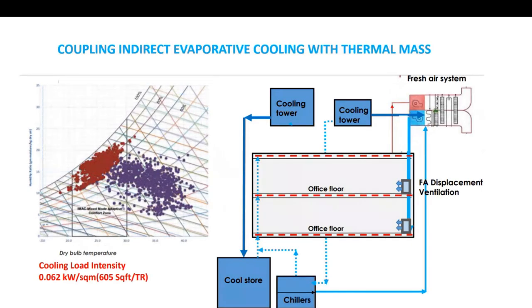Making use of the very dry climate of Hyderabad, we install a highly efficient cooling tower, which has about a 1 to 2 degree approach to wet bulb. We store that cool water in a big store in the basement, and this water is then circulated through the slabs for radiant cooling. There's a chiller added online, so to speak, to add a bit more cooling if required, and the chiller can also help run the fresh air system.